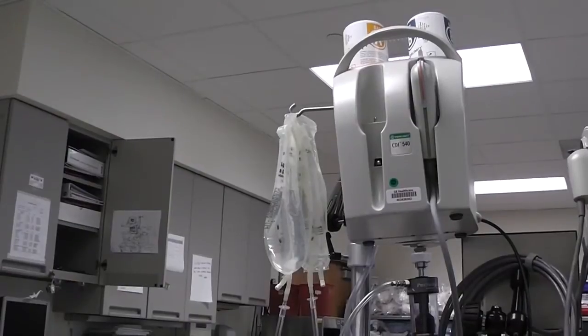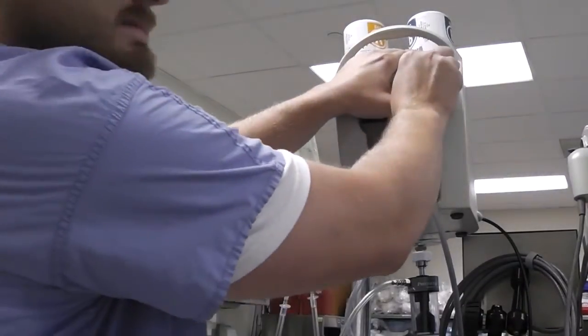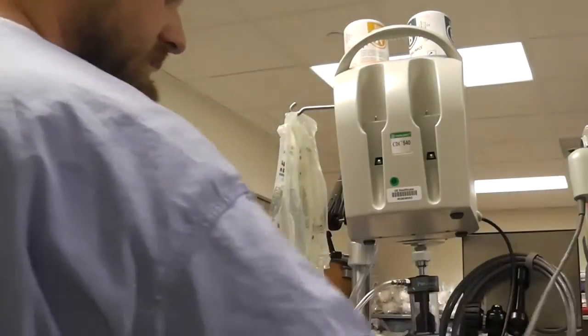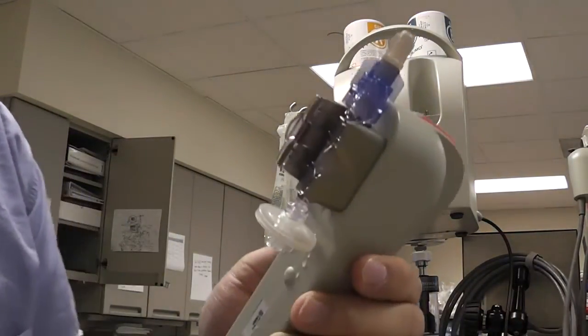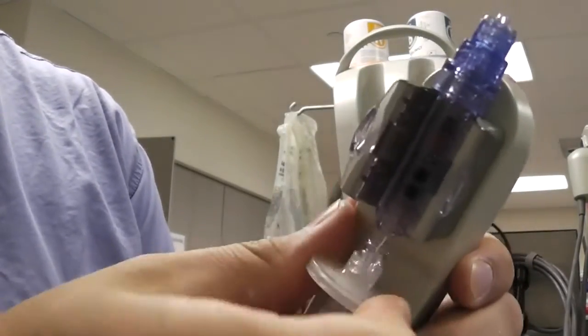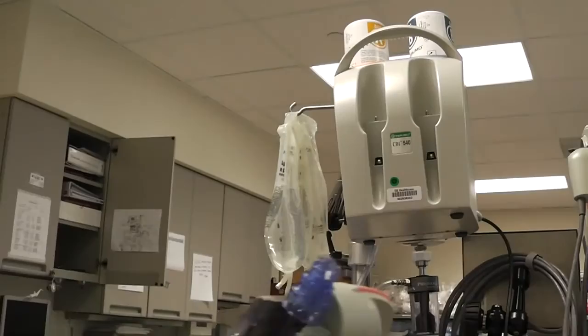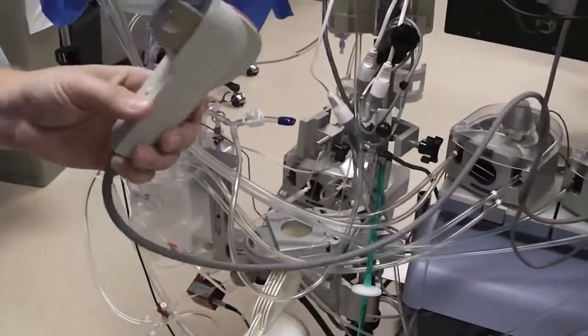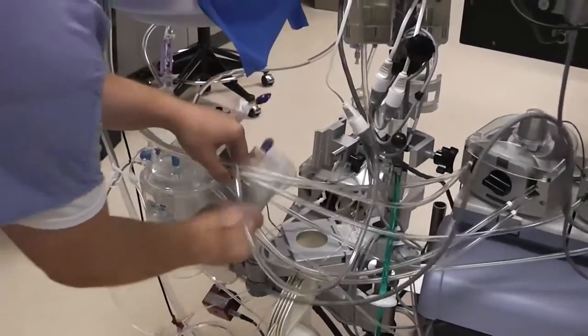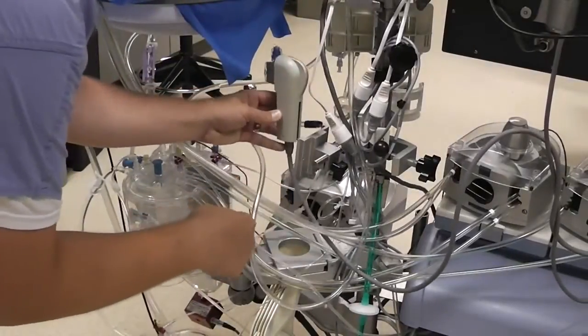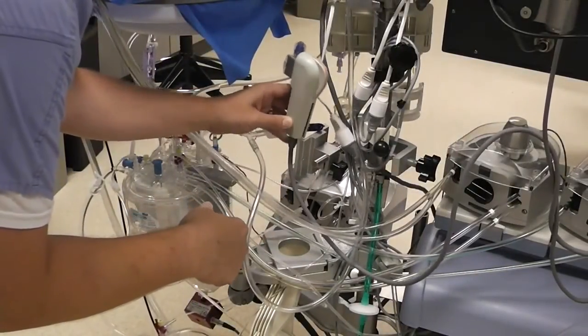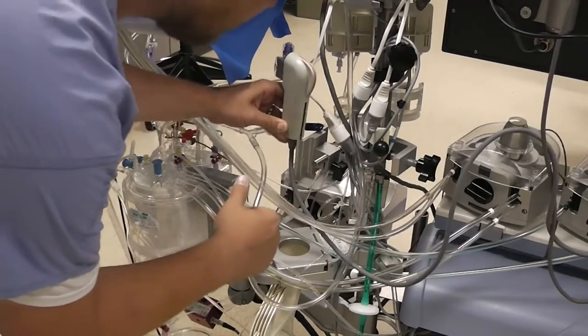After the CDI is done calibrating, we can remove this and take out all the line. Now on this CDI sensor here, we want to close that blue cap back up. We want to remove the white cap from the top and the filter from the bottom. Now we're going to put that in its holder. Snake it under the vent and sucker lines and push it onto its holder here.